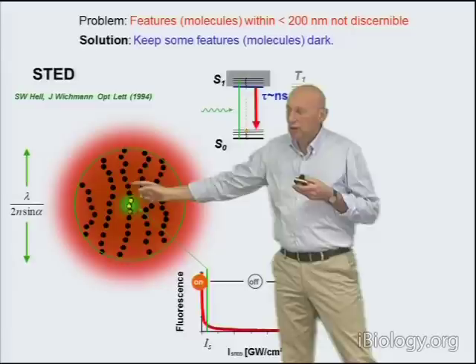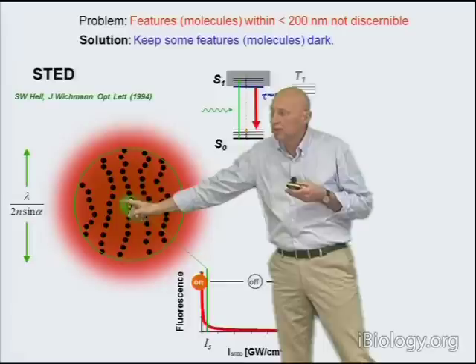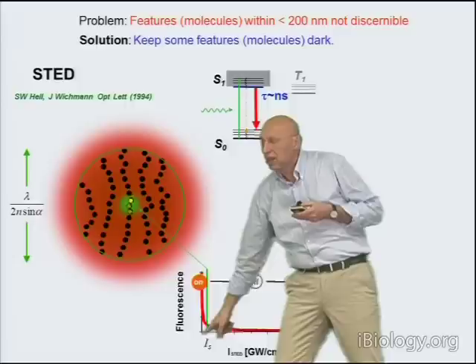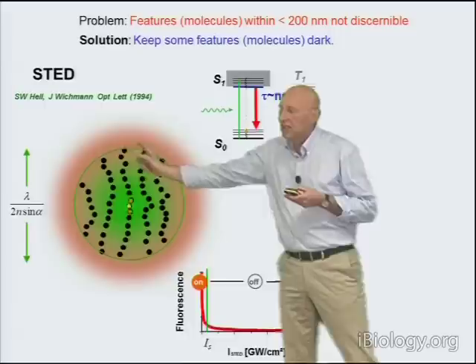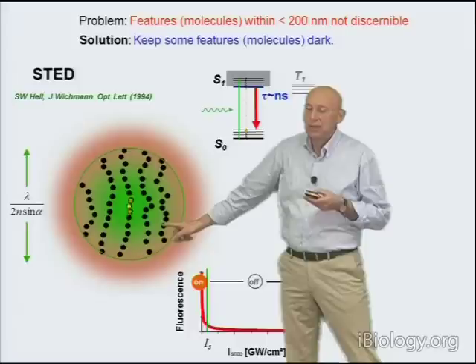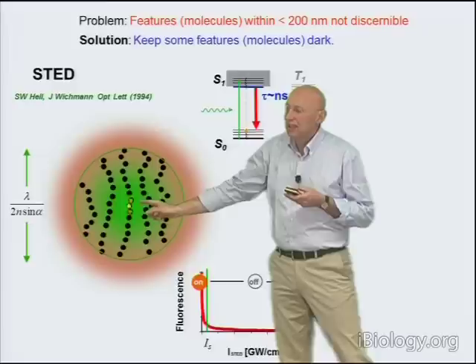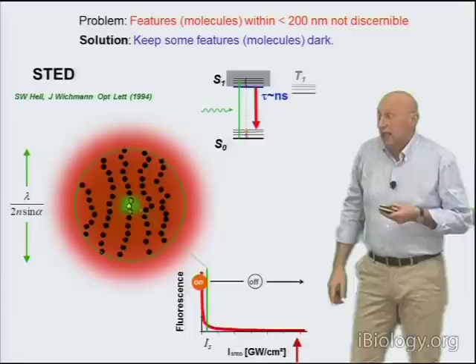We have shaped the STED beam into a doughnut pattern because we don't want to shut off all the molecules — we want to see some. We want to discern features like one microtubule from another. So we want to keep an area where the molecules are still capable of emitting. This area is where the intensity of the doughnut is smaller than the threshold intensity IS. Despite the fact that all molecules are covered with excitation light, only those in this central region are allowed to emit — the rest is silenced. This is the basic principle of STED microscopy: only a subset of molecules is capable of emitting within this 200-nanometer zone, namely a subset located at a specific position predetermined by the shape of the STED beam.